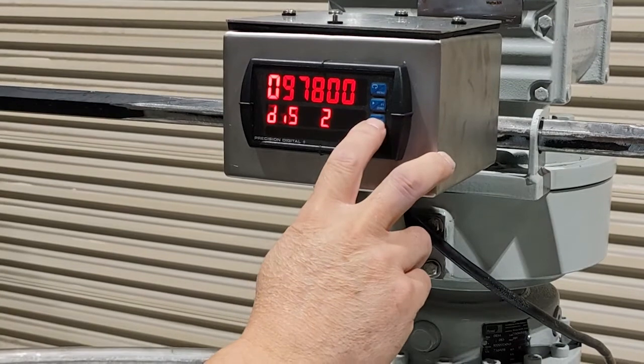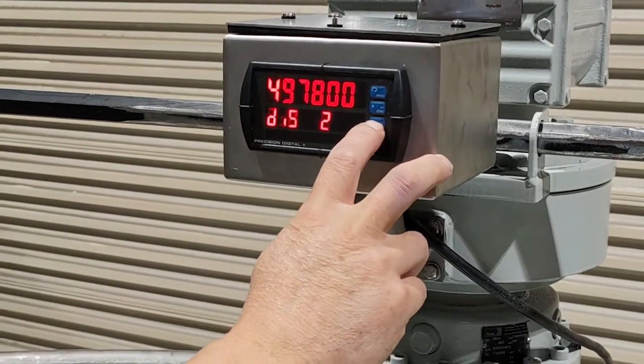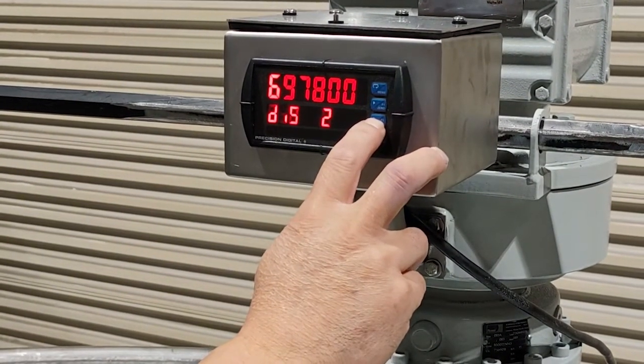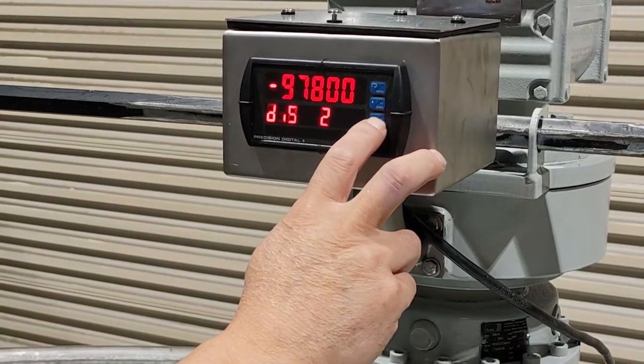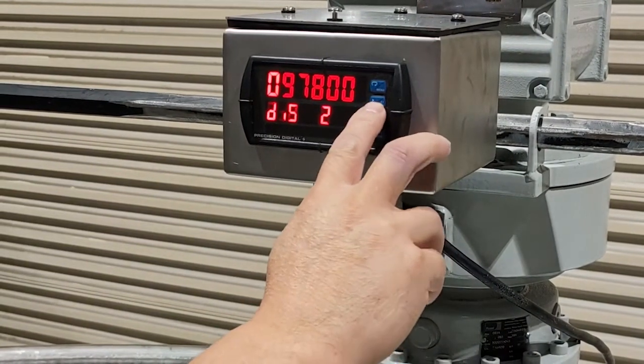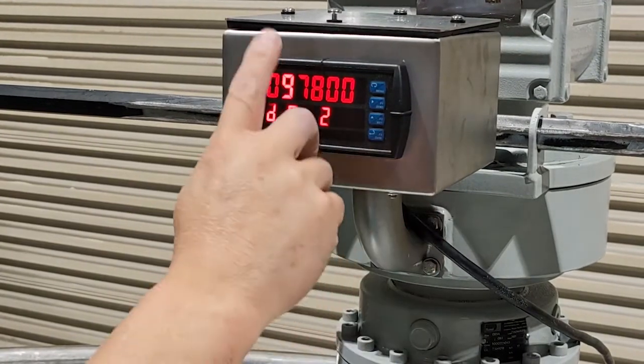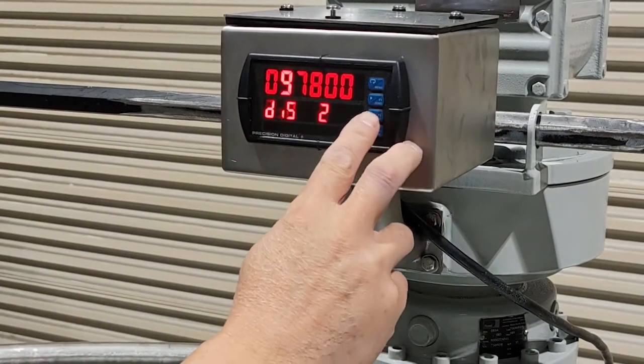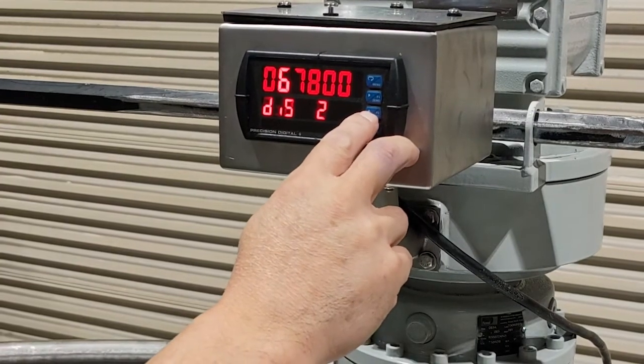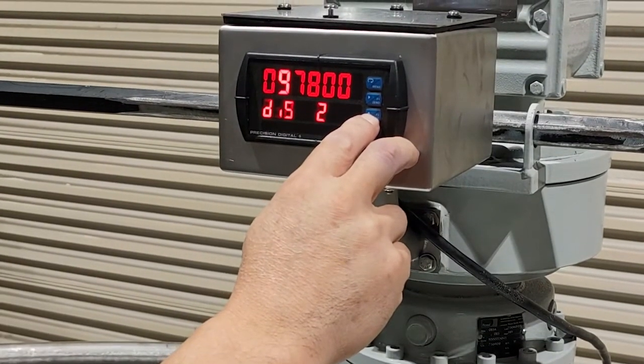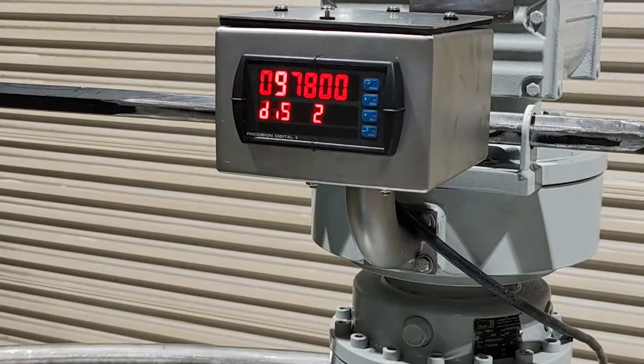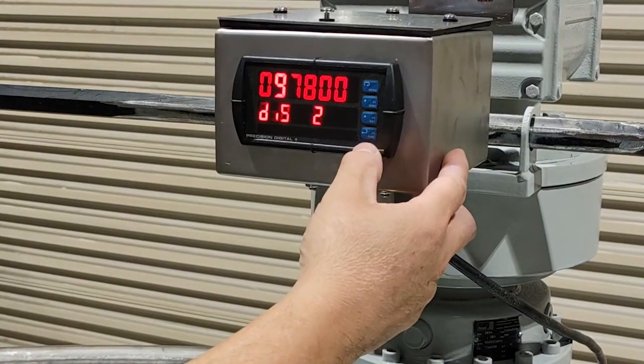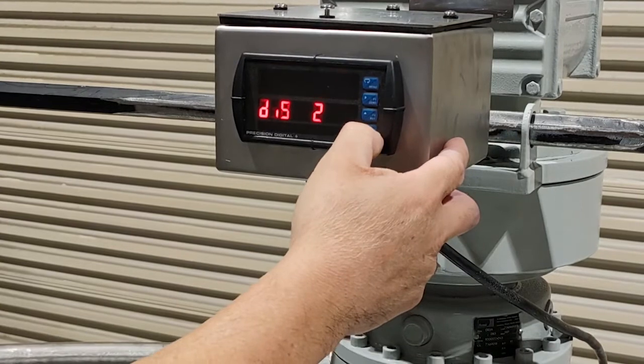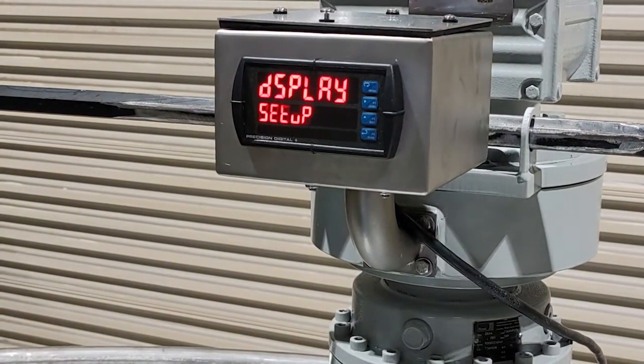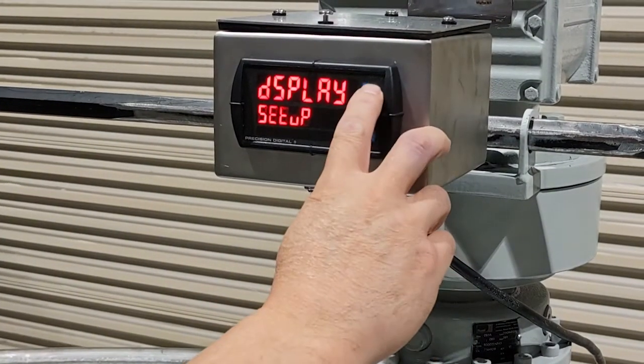Starting from the leftmost digit of the display, use the Scroll Up button to increase the value, and use the Next button to select the correct digit and move to the next one. Repeat until all digits have been selected. Once the display matches the value on the calculation sheet, press the Enter button to confirm the setting. Press the Menu button to go back to the main display.